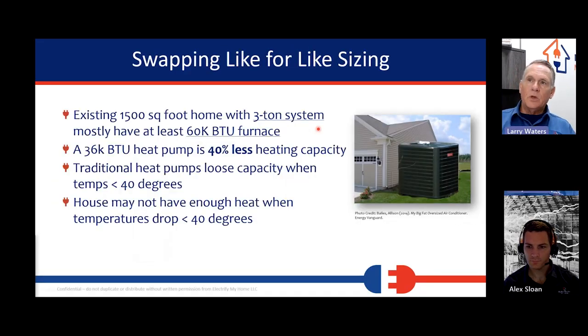Okay. Swapping like for like sizing, existing 1,500 square foot house, there it is again. 3-ton systems mostly have a 60,000 BTU furnace. The new heat pump is going to have 40% less heating capacity. And heat pumps lose a lot of capacity when it gets below 40 degrees outside. That's why for years we've combined them with furnaces or strip heaters or backup heat to kick in when the temperature gets lower. If you're putting in a heat pump system that needs some alternate heating because it's going to be cold outside, you're not putting in the right heat pump system.